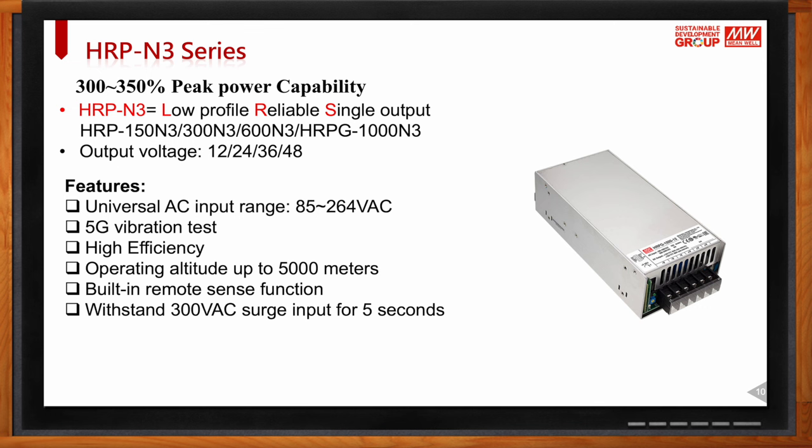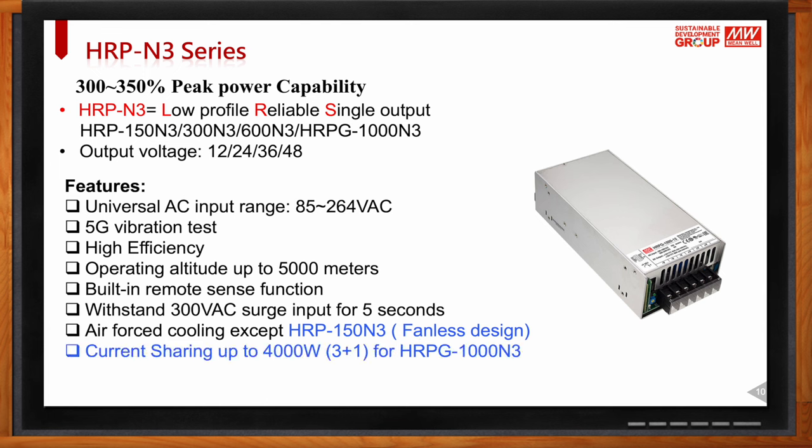The HRP can operate up to 5000 meters altitude, has a built-in remote sense function, and withstands 300V surge input voltage for five seconds. All HRP models use forced-air cooling except the HRP-150, which is fanless. For customers needing more power, the HRP-1000 supports current sharing — up to four units in parallel for up to 4000W total.